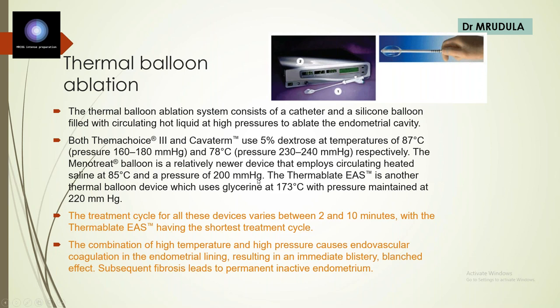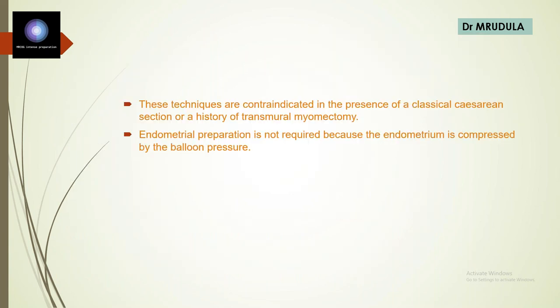What you have to remember is that circulating hot liquid is used to ablate the endometrium. The treatment cycle varies between 2 to 10 minutes. The mechanism of action for thermal balloon ablation is that high temperature and high pressure cause endovascular coagulation in the endometrial lining, resulting in immediate blistering and blanching effect, and subsequent fibrosis, causing endometrial ablation.